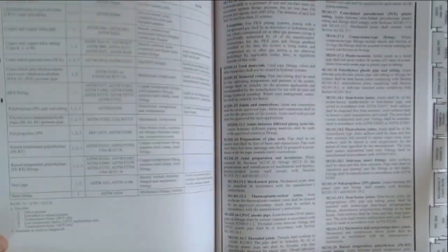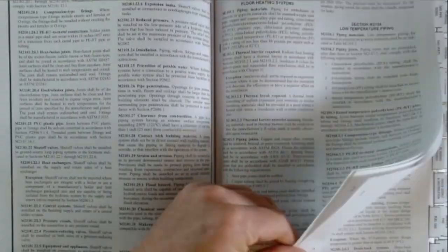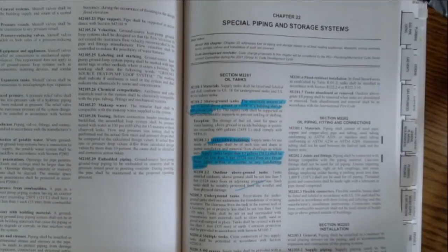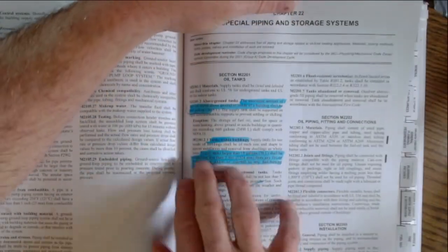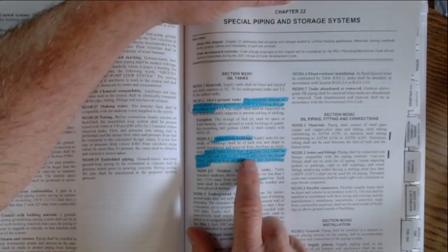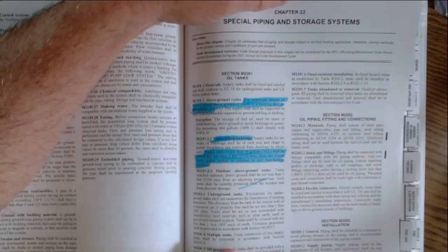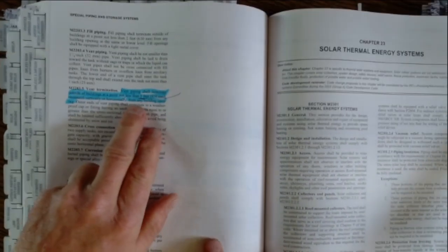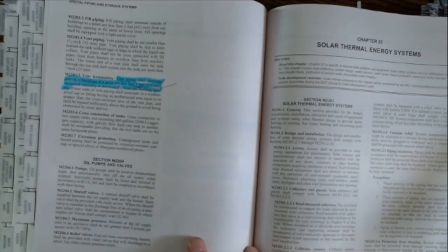Water heaters. Yeah, if you're using a water heater for space heating, it has to be potable water. You can't have fuel-fired water heaters in closets. Hydronic piping, heating piping has to be sleeved if it's going through masonry or concrete. Okay, if you have like a fuel storage container in your basement, 660 gallons is maximum. If it's more than 10 gallons, it'd be 5 feet away from any flame source. And you're going to have a venting going out to the outside. It has to be 2 feet away from any opening.